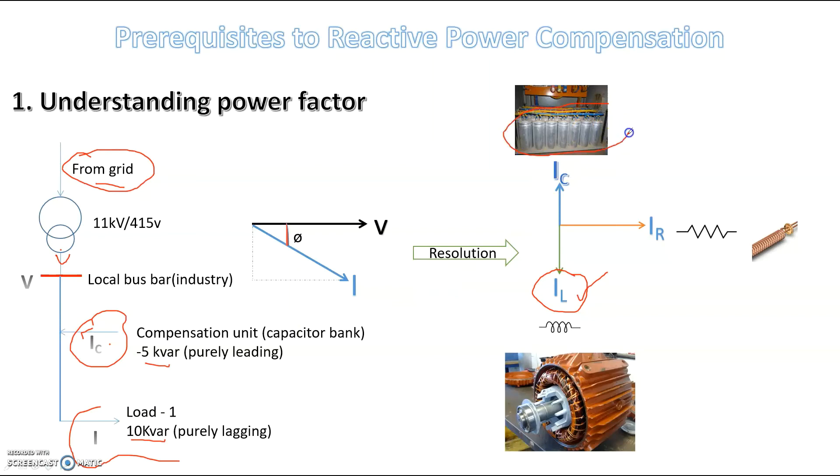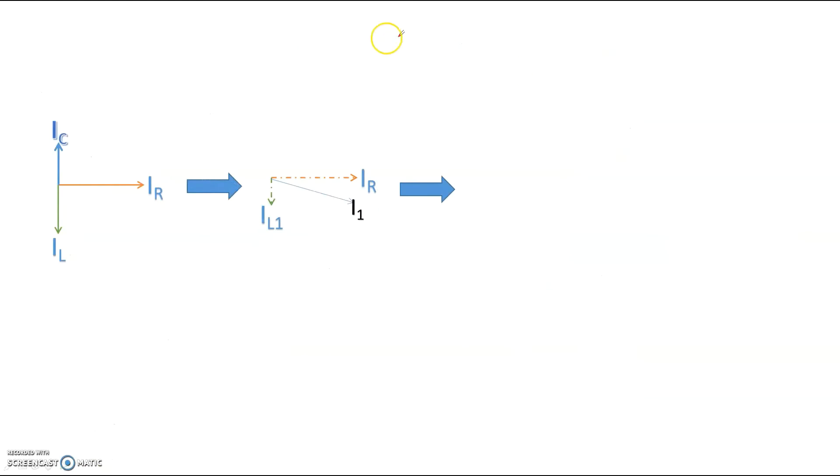If you understand here, if I have the current IC here, which is going to negate the effect of IL, what will happen is, the value of IL will reduce to IL1 and the current I1 will be this. You have to observe that this particular angle is reducing. This would be the new scenario after tapping the capacitor bank. This will be phi 1. Earlier, we had this scenario when no compensation was there, no IC was there. So you clearly can understand here that cos phi 1 is greater than cos phi. So the power factor is basically improving.